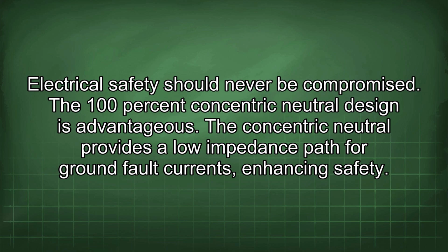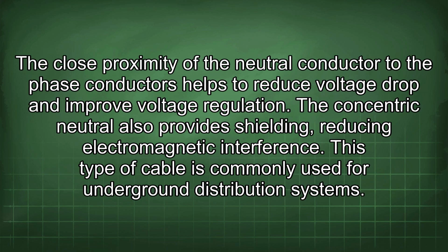The 100% concentric neutral design is advantageous. The concentric neutral provides a low impedance path for ground fault currents, enhancing safety. The close proximity of the neutral conductor to the phase conductors helps to reduce voltage drop and improve voltage regulation. The concentric neutral also provides shielding, reducing electromagnetic interference. This type of cable is commonly used for underground distribution systems.